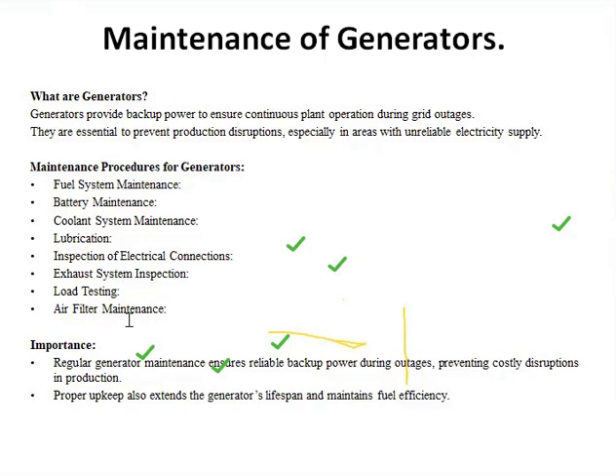So these generators also have some maintenance procedures that I always check on daily, monthly or annually. So I always check on the fuel system. The fuel filter must be replaced regularly to avoid blockages. For example, if the fuel filter in a diesel generator clogs, the engine may sputter and eventually stop. So I think last week but one, we had some problem with our fuel filter. We could not start the generator; it shows that it is starting and then stops immediately. So by checking the fuel system, we managed to fix that.